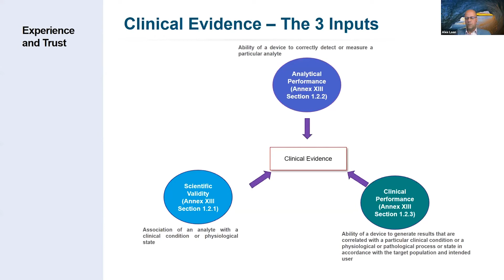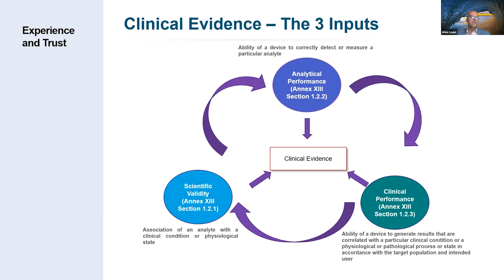But for very new analytes, it may not be so easy to demonstrate, and it may also not be so clear. Also, knowing that a lot of tests have been placed on the market without establishing the scientific validity of the analyte, you may sometimes come to surprises. All of that needs to be gathered as clinical evidence. Analytical performance, you typically document in an analytical performance report. Clinical performance, you document in a clinical performance report. Scientific validity in a scientific validity report. And you can collate that together in a performance evaluation report.